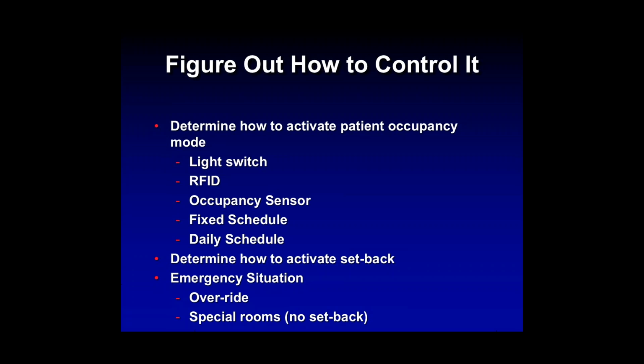So what we're planning on doing is utilizing our surgical schedule, and we'll look for the first case to take place, and we'll set it back to the 20 air changes per hour 30 minutes before that first case hits the room. And then we all know that the surgical schedule never really follows exactly the way it was planned, and so there could be add-ons or cases taking longer than scheduled. And so we're looking at the schedule and saying, after that last scheduled case takes place, we're going to look for an indication that the surgical light is shut off to actually start it into the setback mode. And we'll add 45 minutes onto that to purge the room.